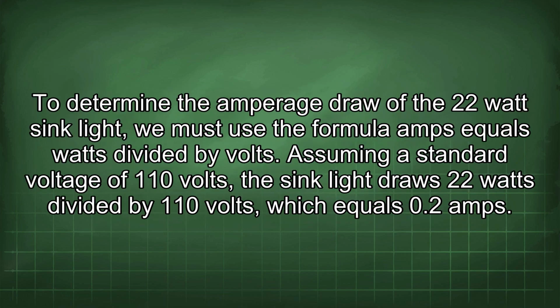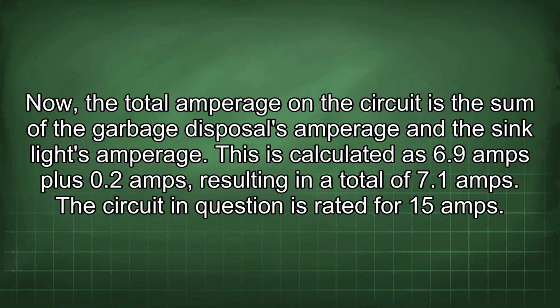To determine the amperage draw of the 22-watt sink light, we must use the formula amps equals watts divided by volts. Assuming a standard voltage of 110 volts, the sink light draws 22 watts divided by 110 volts, which equals 0.2 amps. Now, the total amperage on the circuit is the sum of the garbage disposal's amperage and the sink light's amperage. This is calculated as 6.9 amps plus 0.2 amps, resulting in a total of 7.1 amps.